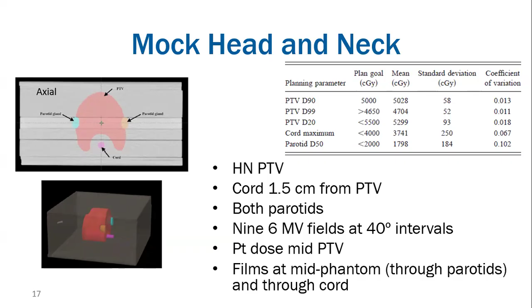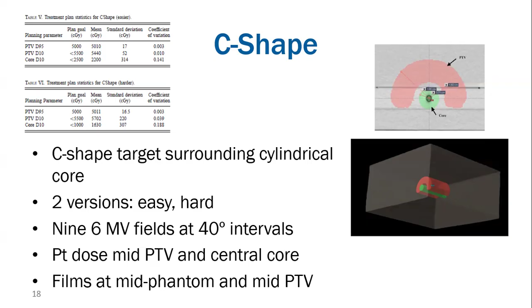And then the last pair of plans that they talk about in TG119 is a C-shaped plan. So basically, this is not anatomically motivated, but it's designed to really push your system to the limits. And the idea is that there are two versions of this plan. So in both cases, the PTV is supposed to get 50 gray, but then in the easier case, the organ at risk core that's in the center is supposed to get 25 gray. And then in the harder version of it, again, the PTV is supposed to get 50 gray, but then the inner core is supposed to only get 10 gray. Here they also use 6 MV fields at 40-degree intervals. They measured point dose at the PTV and in the central core, the organ at risk, and then film at mid phantom and mid PTV.